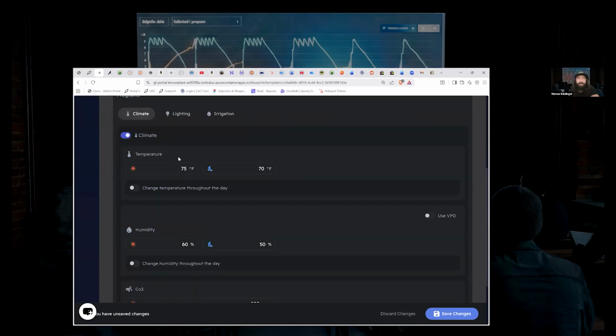To start, we've got our temperature. We've made it kind of simple. If you've ever used our dynamic rules in the set points drawer, this is essentially that, where we have a singular set point that all the rules for the room are going to be pulling from. We're going to set up our rules on the room, and we will go through that maybe today, maybe not today, but either way, the actual rules that dictate your dead bands and things like that for all of your different devices are going to live on the actual room.